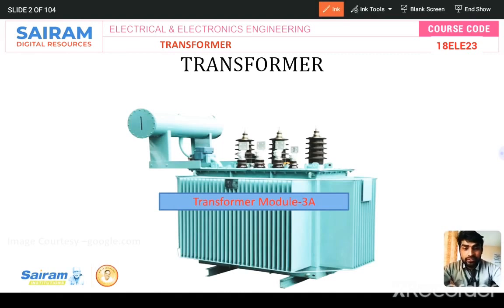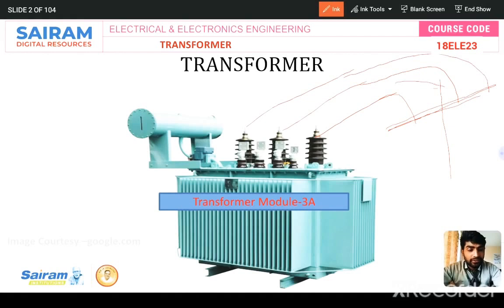Here there is the 3 phase input. These are the bushings, and here I place the transmission lines, disconnected here and here, and this connected here, and one neutral wire will be there. If neutral is present, that is star connected. If it is delta, no need of neutral, only 3 wires will be there. Otherwise 4 wires will be there, which definitely means neutral is present.